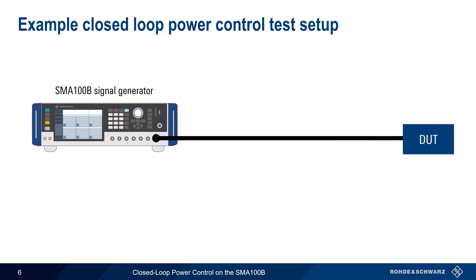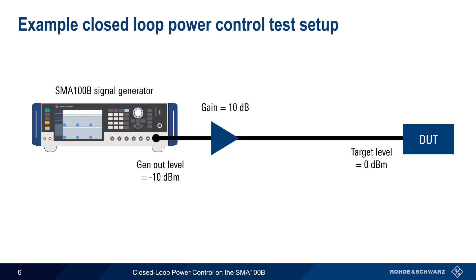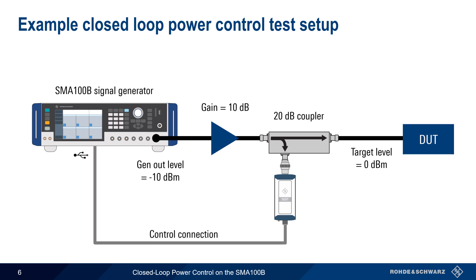Let's go through this step by step. Here we're using an SMA100B analog signal generator to provide power to a device under test. Our desired signal level or target level at the DUT is 0 dBm. An amplifier with a nominal gain of 10 dB is downstream from the SMA, so the SMA output power would be set to minus 10 dBm in order to have a level of 0 dBm at the DUT input. Since the gain of this amplifier may change based on frequency, temperature, etc., we implement closed-loop power control by placing a 20 dB directional coupler in the path. An NRP series power sensor is connected to the coupled port and is connected to the SMA over USB, LAN, etc.